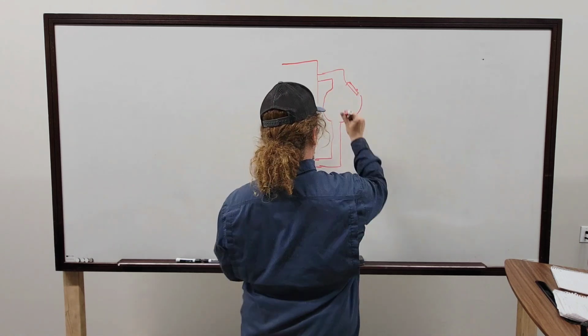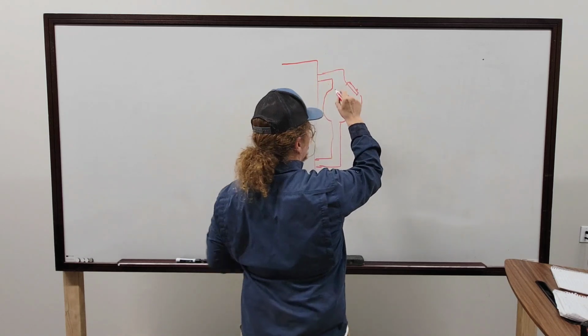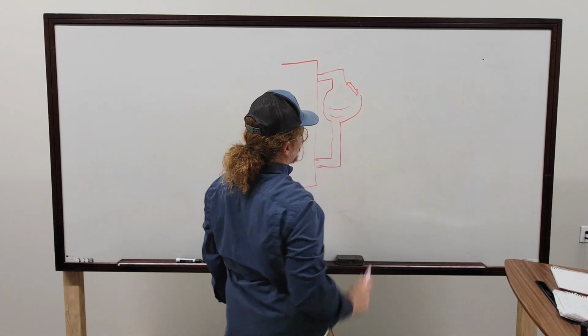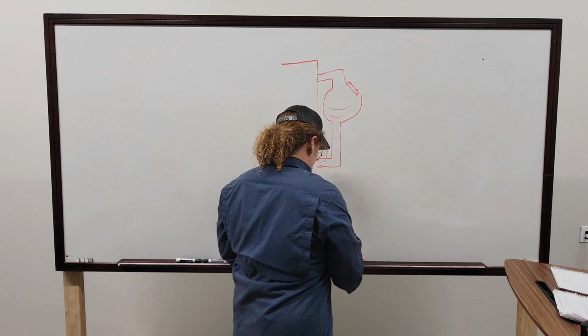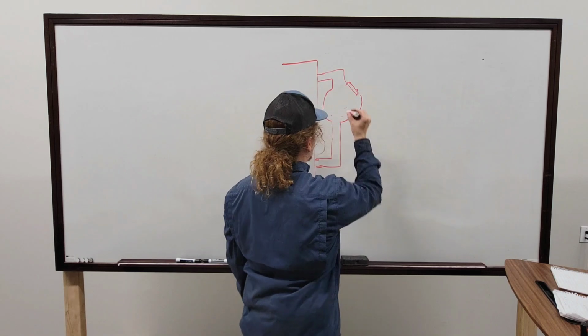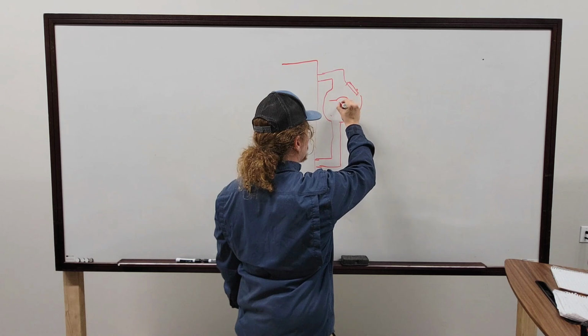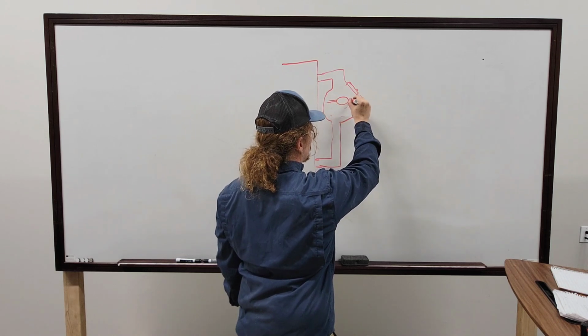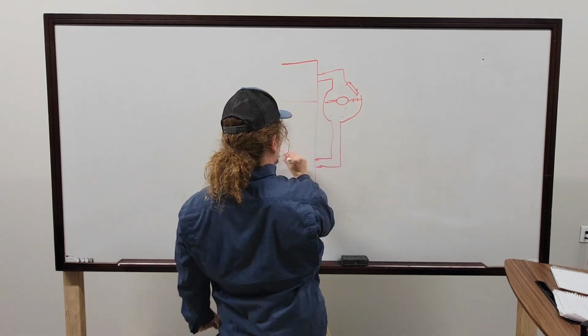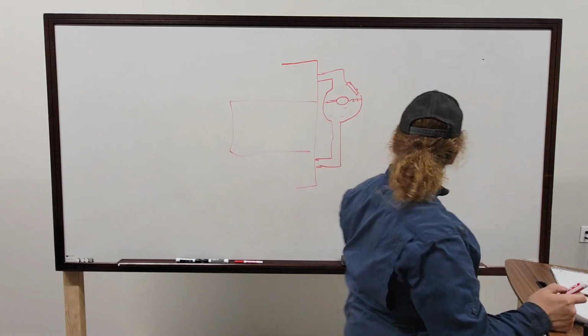All right, so from the front of it, you just see the pipe and a bulb. It's cast iron. But internally it is literally a float, like you would see on a cooling tower, or the back of a toilet. It comes out here, sees a level of water, which is the same water level that is in this boiler. Typically you'll see this on the fire tube boilers, right?